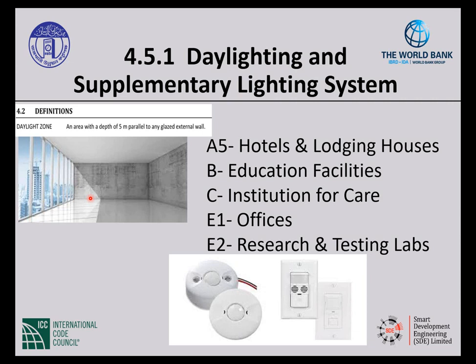This brings up a good point for when we're testing those controls. Usually when we're verifying that things work, we look at the daylight sensor. Does it work? Yes. We look at the occupancy sensor. Does it work? Yes. But are you looking to see that the occupancy sensor and the daylight sensor work together? That occupancy sensor truly is overriding and keeping that daylight sensor from coming on. A lot of times what happens is we don't look at how they work together, and so they fight each other and no energy is saved. So just something to keep in mind.